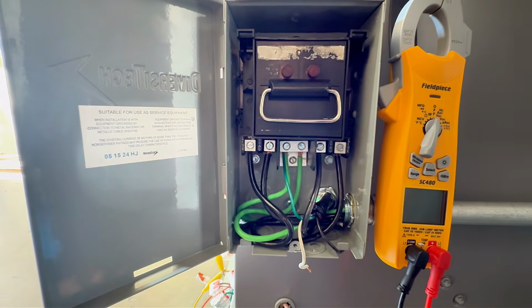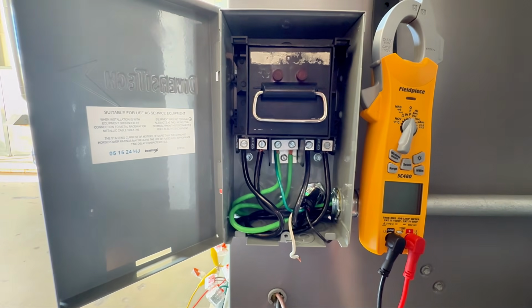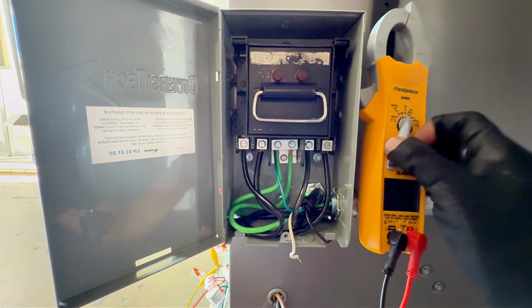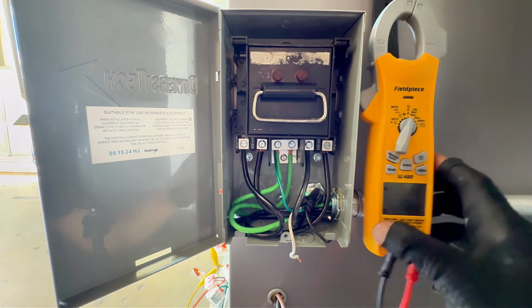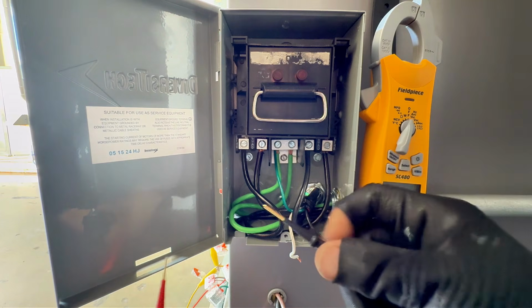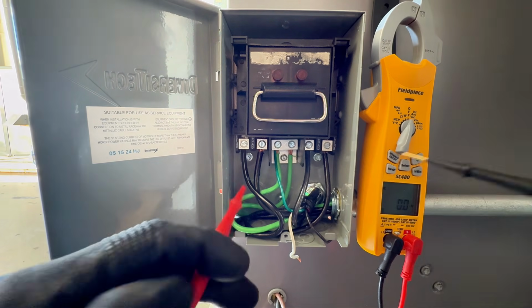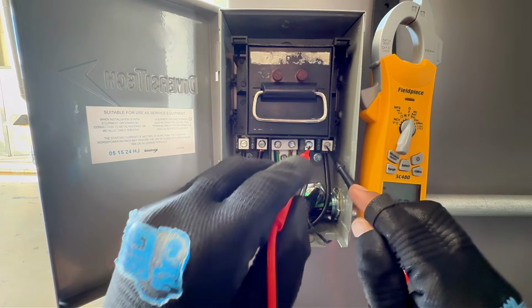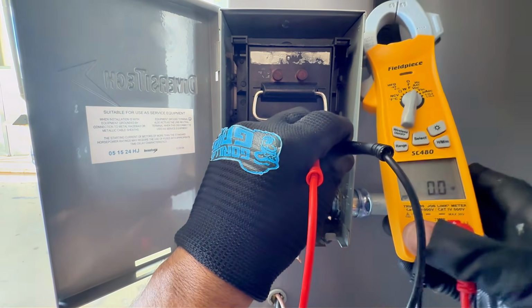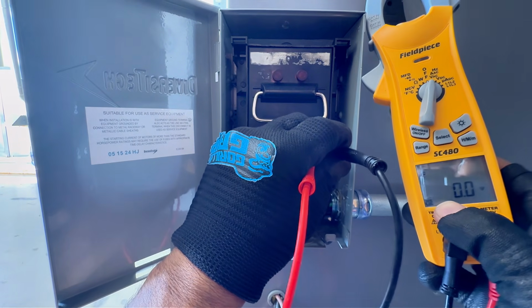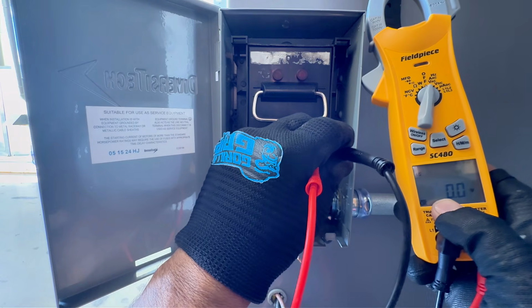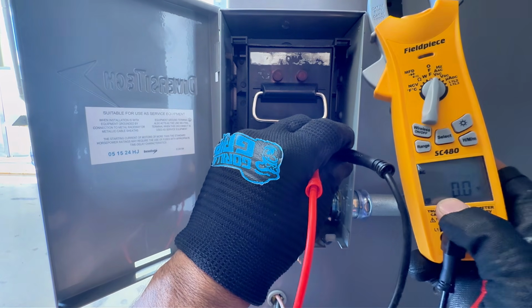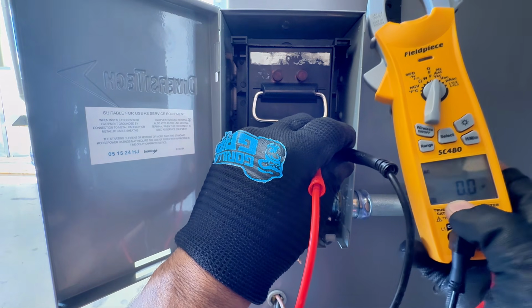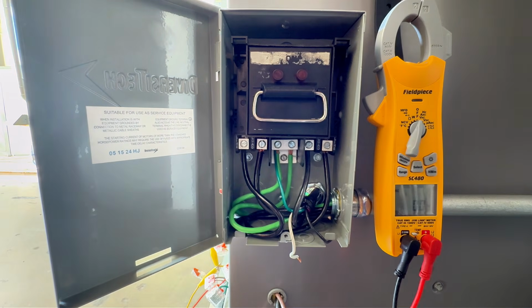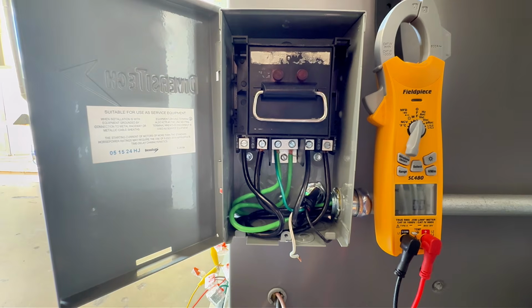Okay, turned on. Now this might not work, and this is where having a thermal camera would work out, but I have seen this work on a breaker to see if there's a voltage drop, and if there is, there's something going on in that breaker. But typically you can check your line and your load, and if you see anything greater than 2 volts, then it's bad. There's something going on. In this case, it's just the line. There's not enough resistance. It's okay, but that doesn't mean there's no issue though. The right way of doing it, and this is where you would have to invest, is getting a thermal camera.